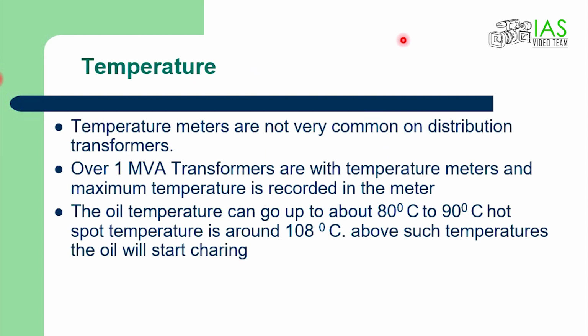Temperature meters are not very common on distribution transformers, but on bigger transformers, temperature meters are there. The top oil temperature can go up to about 80 to 90 degrees. And hot spot temperature, yeah, is around 108 degrees centigrade. Actual value is 118. So CB normally specifies 108.